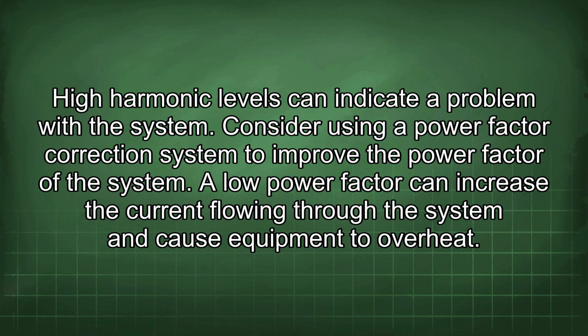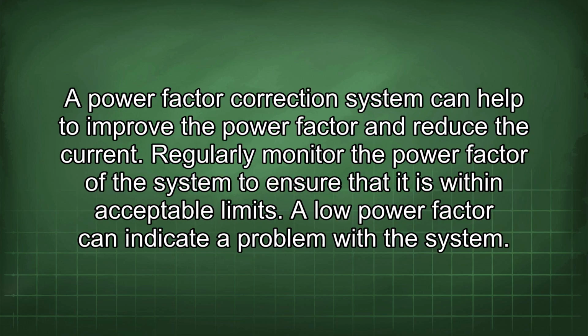Consider using a power factor correction system to improve the power factor of the system. A low power factor can increase the current flowing through the system and cause equipment to overheat. A power factor correction system can help to improve the power factor and reduce the current. Regularly monitor the power factor of the system to ensure that it is within acceptable limits. A low power factor can indicate a problem with the system.